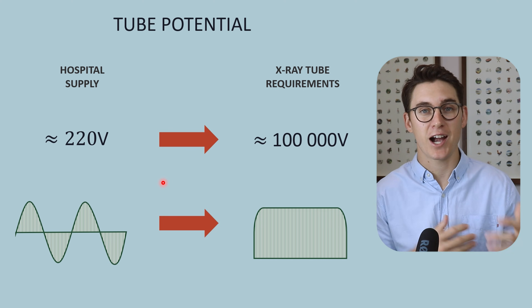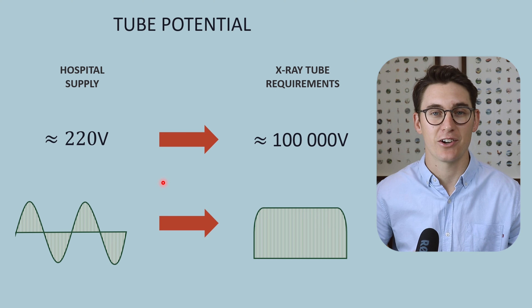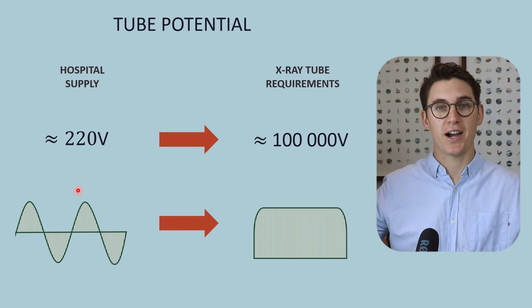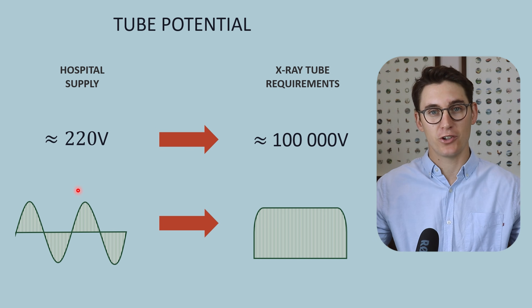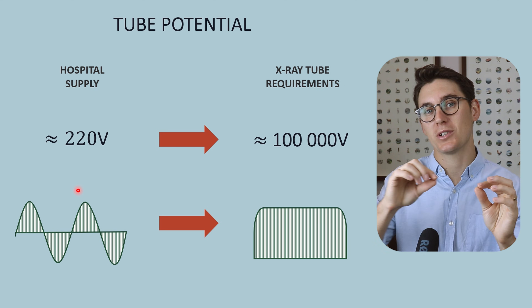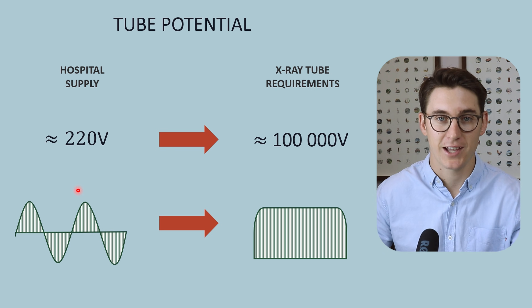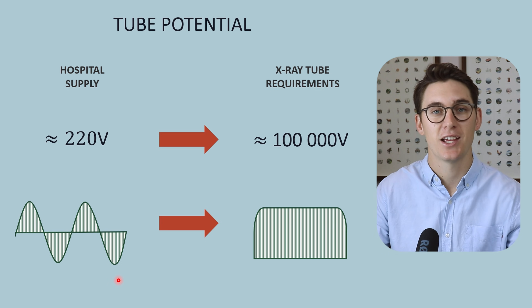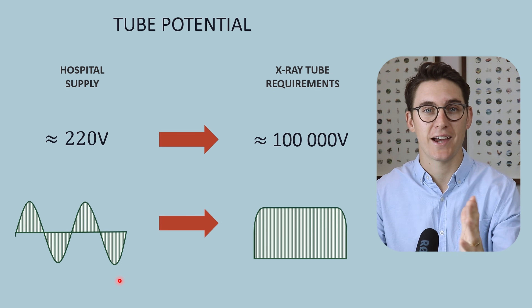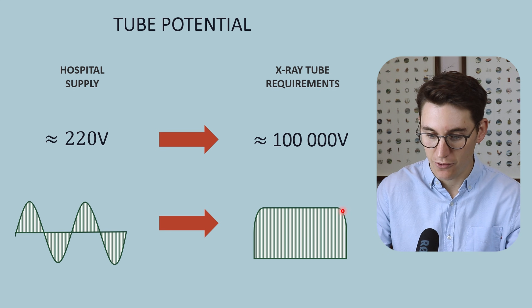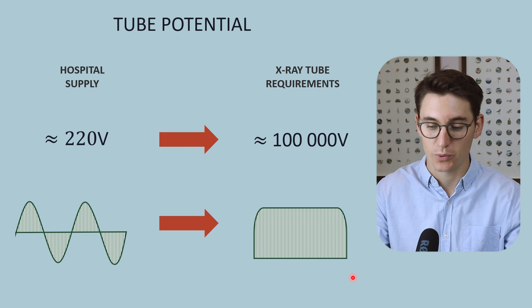The second issue is that the hospital current supply is alternating current — it goes in both directions over time. When providing a tube differential from cathode to anode, we want current flowing in one direction only. We don't want electrons going from the anode toward the cathode. Furthermore, that current is fluctuating, and we want a constant stream of electrons toward our anode. So we need to convert alternating current into direct current and smooth it out so it is constant.